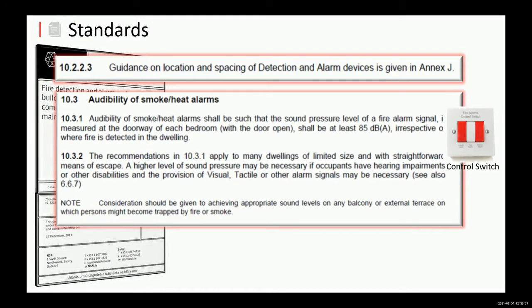There's also a recommendation here, 10.3.1 applies to many dwellings with limited sizes and straightforward means of escape. A higher level of sound pressure may be necessary if the occupants have a hearing impairment or other disabilities, and the provision of visual or tactile units should be used in that situation. And again, you can go on our website to look at those. We have units for deaf or the hard of hearing that would have a flashing strobe, and a vibrating disc that goes underneath the pillow or the mattress.